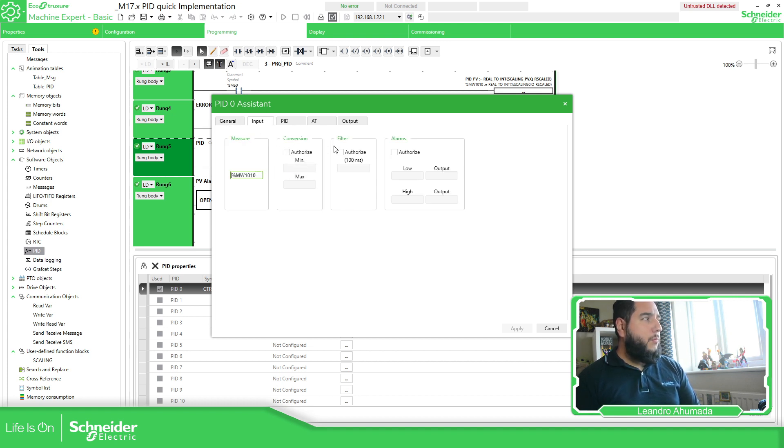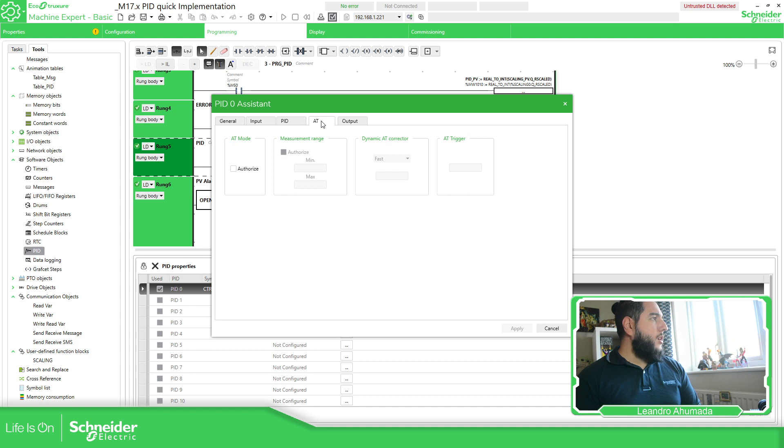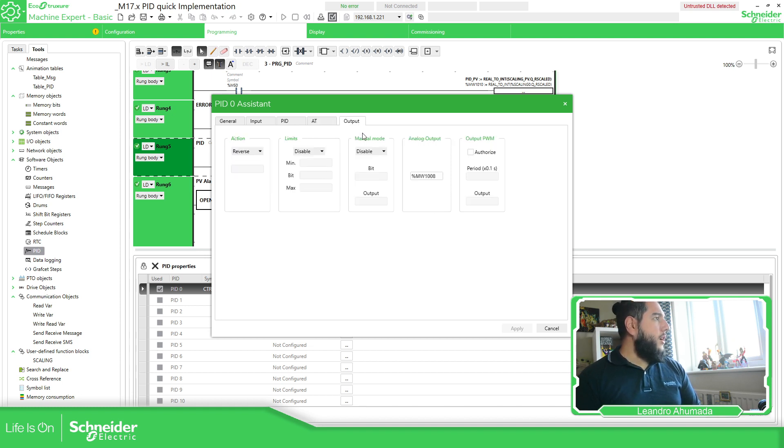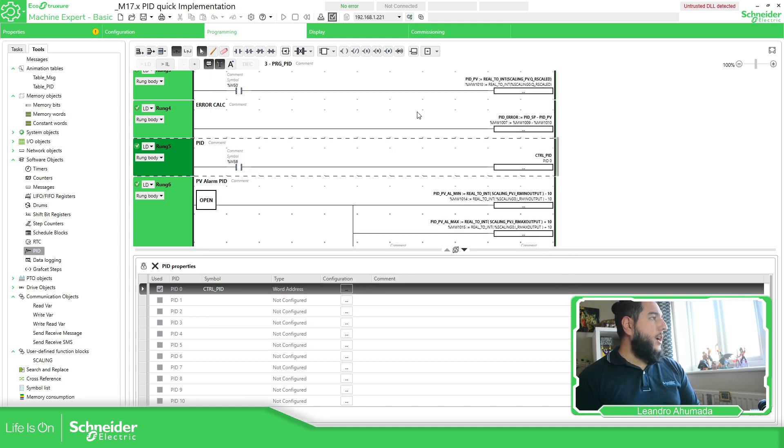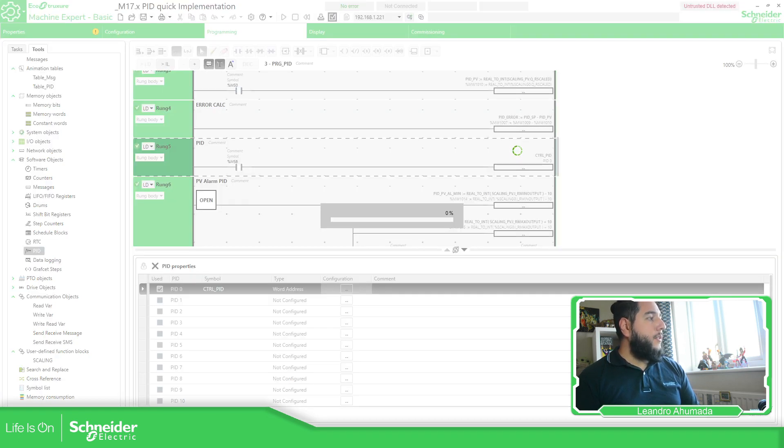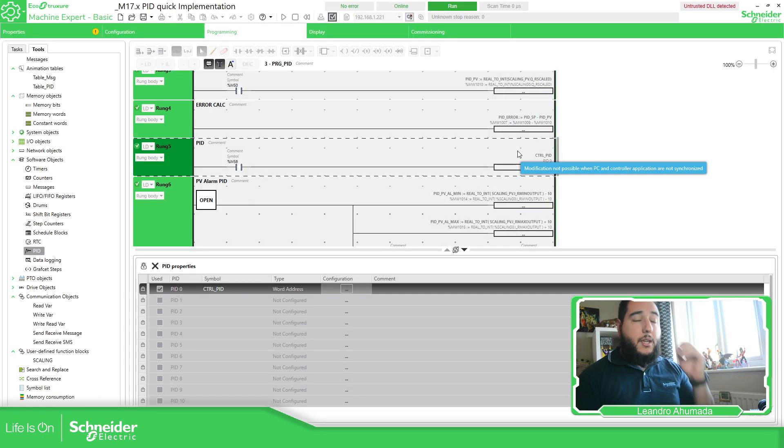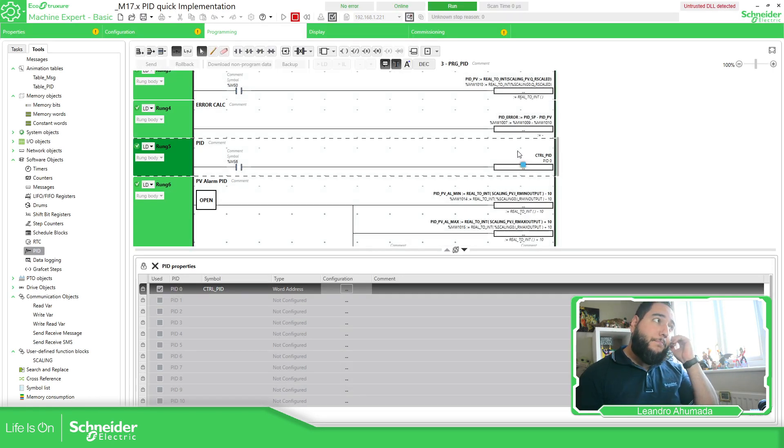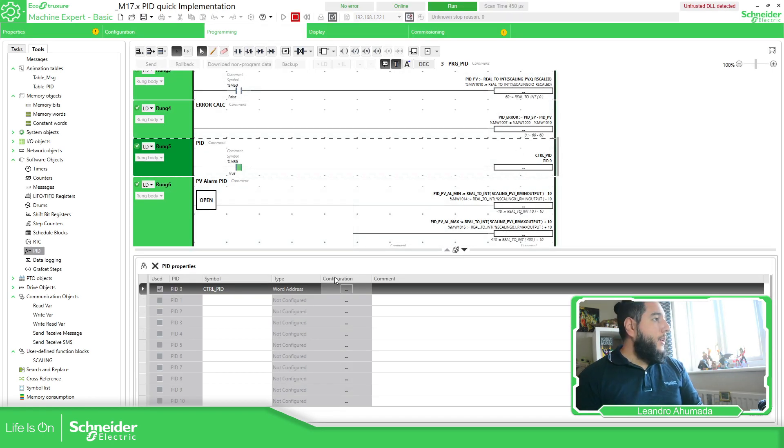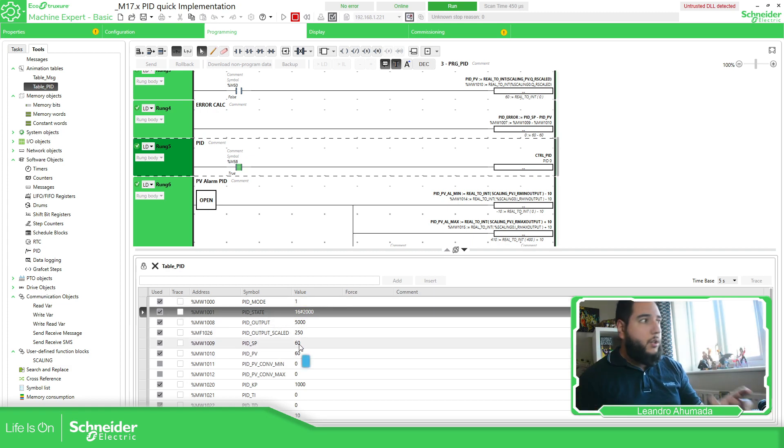So I'm using the word address so I can make some more versatile program here and linking the PID state to this variable. And then I have quickly configured this part. I don't want to use conversion filter or alarms. I link the set point parameters, and I'm going to use autotune in this part and the output just reverse action and the analog output. Once I have all that, I have created this table with the word address, the status, and then the different kind of output and input of the block.